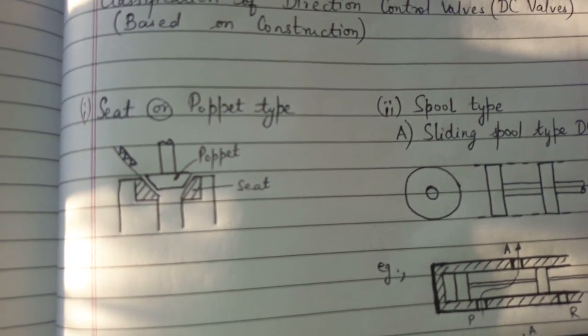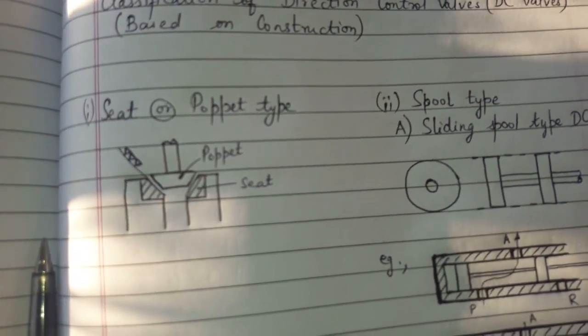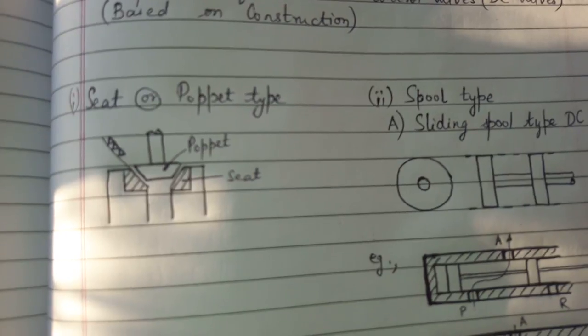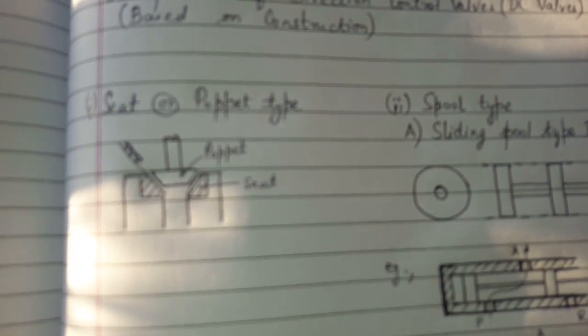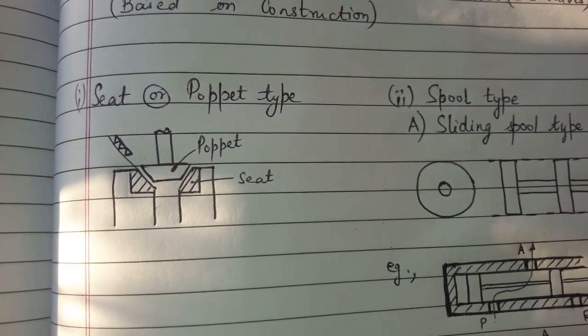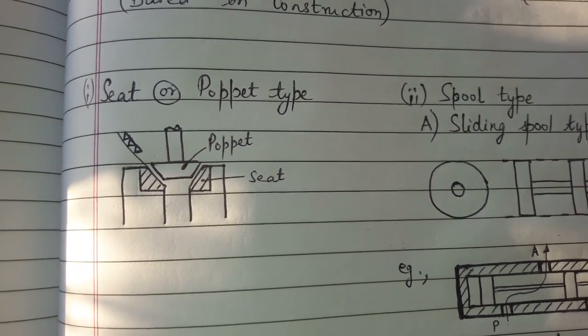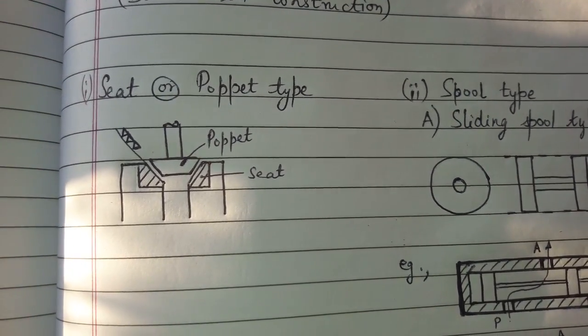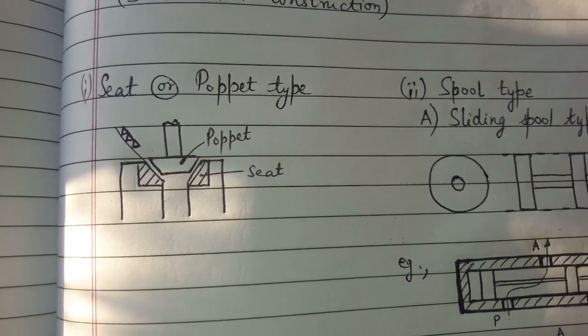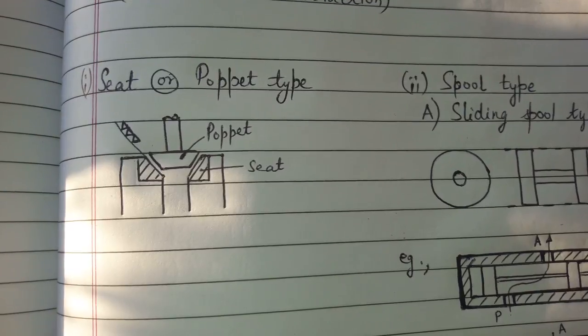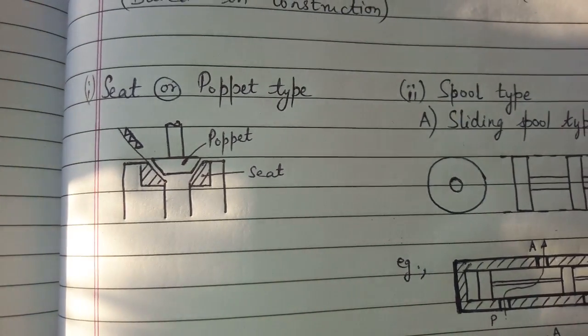The advantage of seat or poppet type are it is suitable for very high pressure application. It has very minor leakage. The disadvantages are seat or poppet type is not suitable for large valve sizes. Due to complicated constructions these valves are costly.